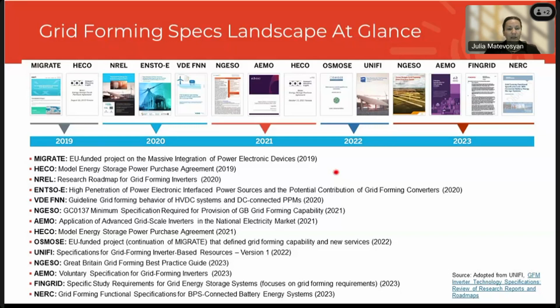DOE-funded project UNIFI has developed a specification for grid forming inverter-based resources, again, high-level functional specifications, and they released it in December 2022. National Grid ESO then supplemented the grid code change with the Great Britain Grid Forming Best Practice Guide. So this guide is basically an application guide to clarify how you verify the performance of a grid forming resource in accordance with requirements that were introduced in GC 137.